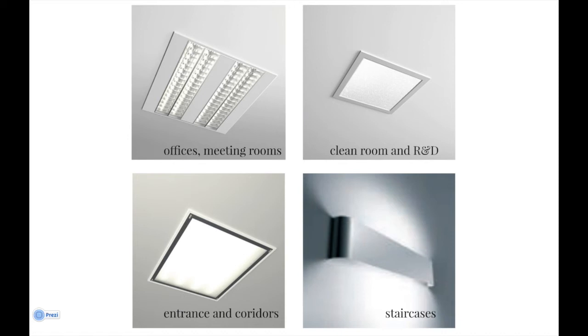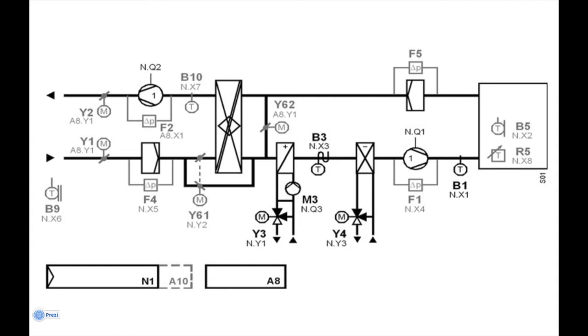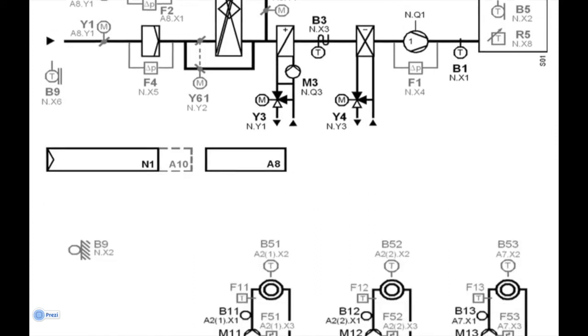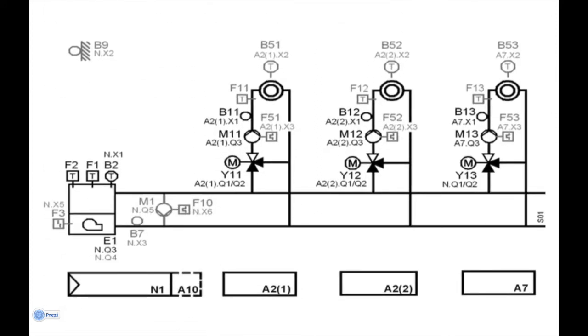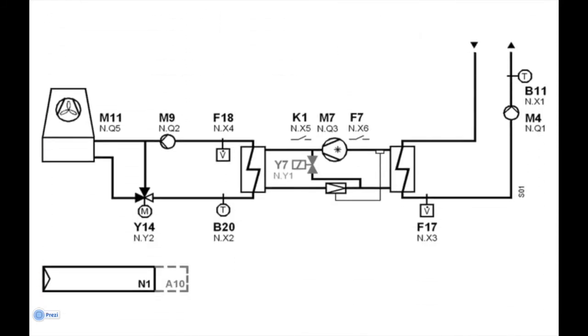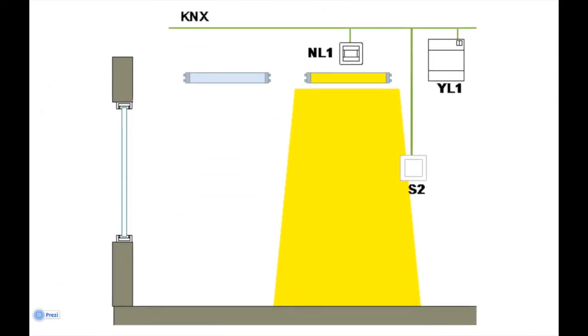Light for entrance, corridors, staircases is chosen to meet criteria from ASHRAE standard 189.1. The automatic control of the air conditioning are cascade, in which we have made use of multiple control loops that involve multiple signals for one manipulated variable. Basic functions of automatic system of boiler are shown here. Automatic control of chilled water generation is shown here. Daylighting control dims or turns off the electric lights in response to the level of natural daylight. Benefits are reducing electricity use, providing a more constant light level, and adjusting to provide range in light levels. Dimming control varies the light output over a wide range to provide the desired light level.